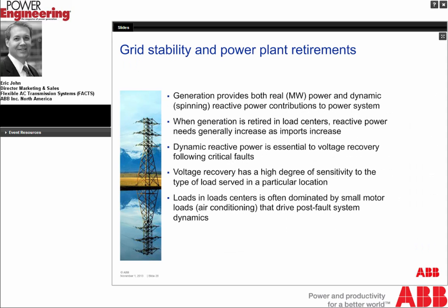Okay, thank you, Russell. So we'll jump right in and summarize some of the key points that John Daniel just made about power generation and the consequences for real and reactive power. The first one is fairly obvious, that generation provides both real power and dynamic reactive power in the form of VARs as contributions to the power system. And when generation is retired in load centers, reactive power needs of the system generally increase as imports increase. And there's an important point to be made here that VARs, or reactive power, are very highly dependent on their physical location in the system. This is due to the nature of the impedance of the power system overall. The underlying physics of the power system mean that VARs are highly dependent on location.